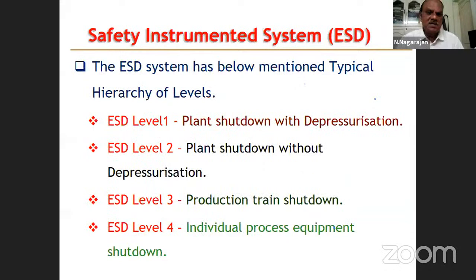The ESD system has different levels. ESD level 1 is the highest level of emergency shutdown. That is when a major hazard has happened. Some big equipment failed, or some tank ruptured, and a lot of hydrocarbons are leaking out of the tank and catching fire. This kind of major hazardous situation is called ESD level 1. At that time, the entire plant will be shut down, and the hydrocarbons contained in the equipment and tanks will be safely depressurized and sent to the flare.